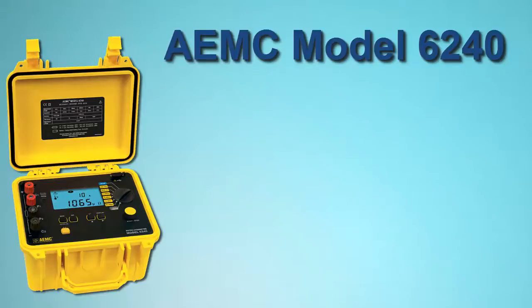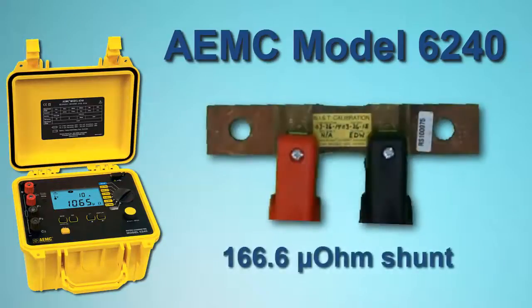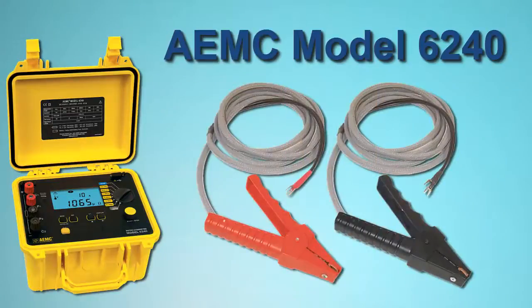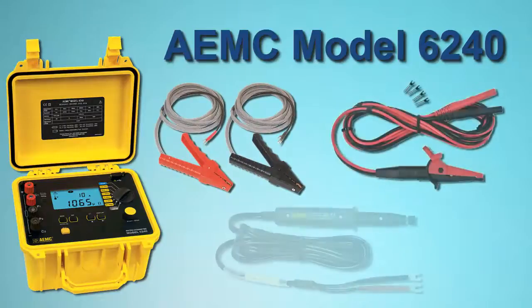For our demonstration, we will connect the instrument to a 166.6 microohm shunt and run a one-minute test with a current of 10 amps. To make the connection, we will use HIPPO type Kelvin clips. The Model 6240 also accepts alligator and spring tip probes.